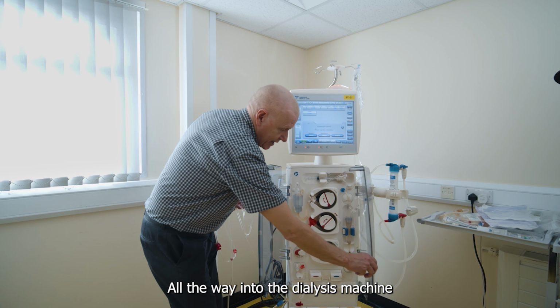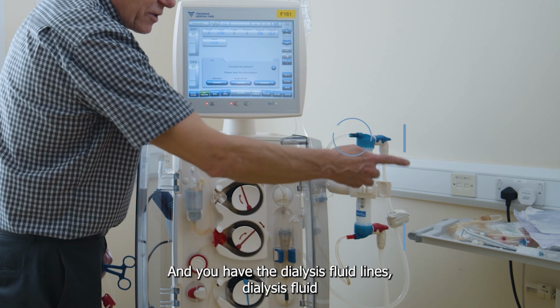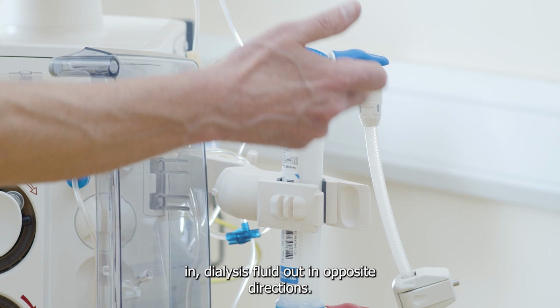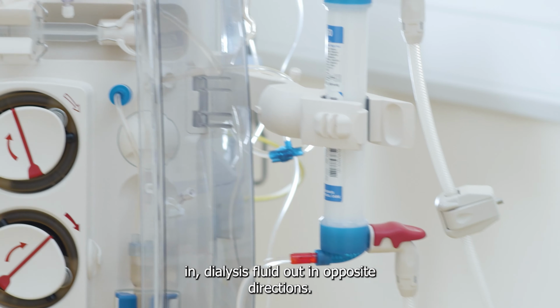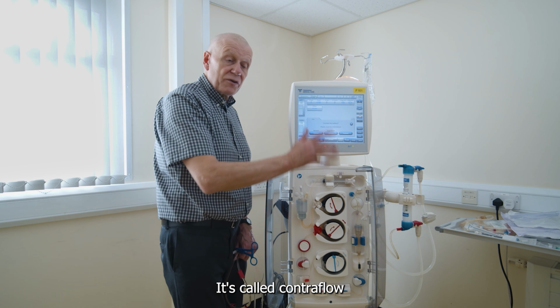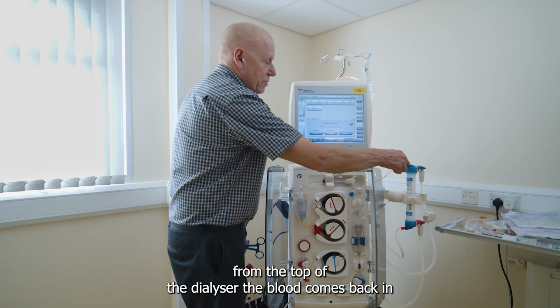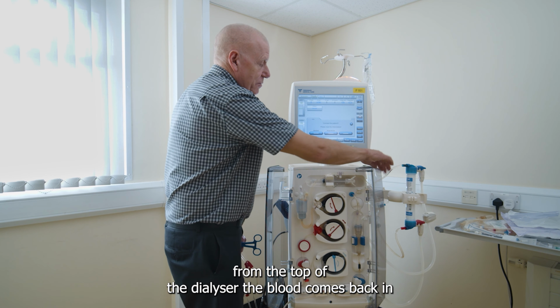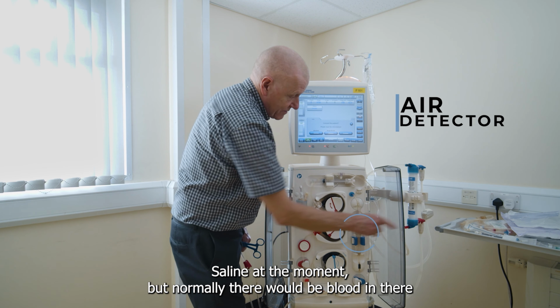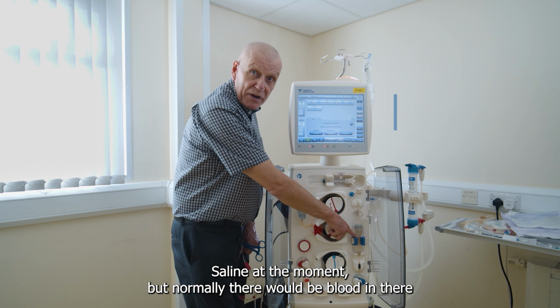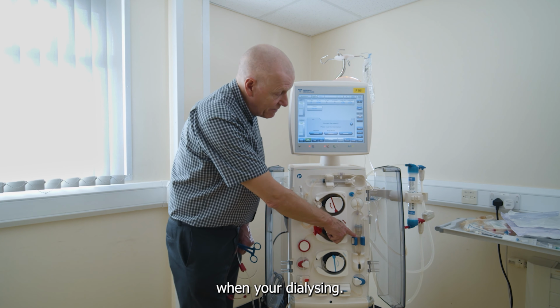You have on the dialyzer the arterial line, blood in, and then the blood out through the venous line. And you have the dialysis fluid lines, dialysis fluid in, dialysis fluid out. They're in opposite directions. It's called contraflow. From the top of the dialyzer, the blood comes back into the machine, to the air detector. This has a level of blood within it. You can see saline at the moment, but normally there would be blood in there when you're dialysing. This detects if there is any air in that blood.